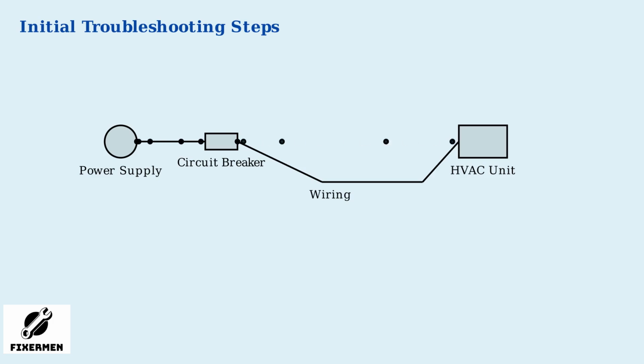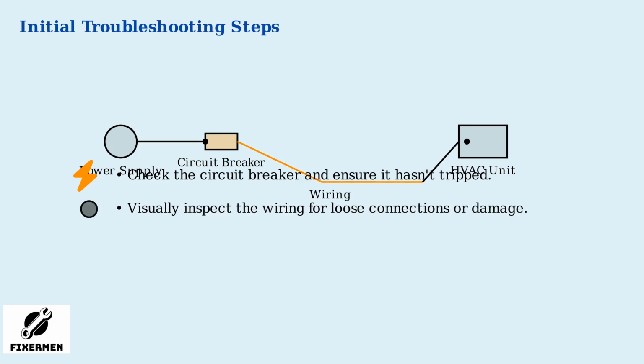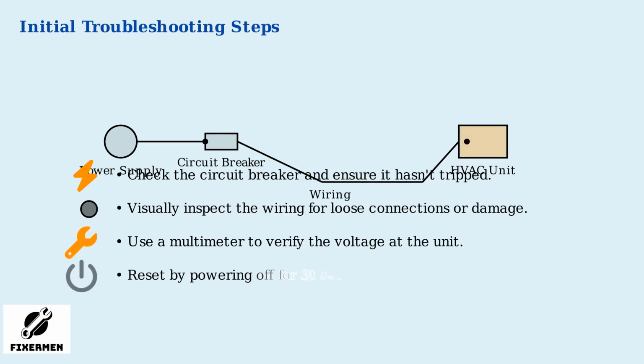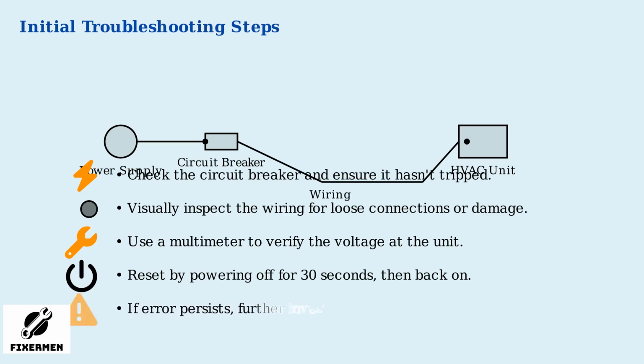When you encounter a P1 error, begin with initial troubleshooting steps. The circuit diagram shows voltage flow from the power supply through the breaker, wiring to the HVAC unit. First, check the circuit breaker and ensure it hasn't tripped. Next, visually inspect the wiring for any loose connections or damage. Then, use a multimeter to verify the voltage at the unit. A simple reset can resolve the issue. Power off the system for about 30 seconds, then turn it back on. If the error persists, further investigation is needed.